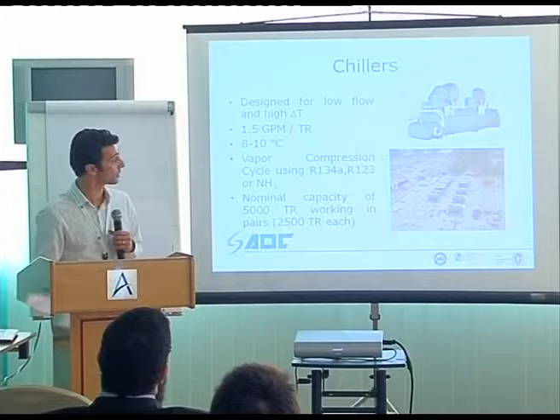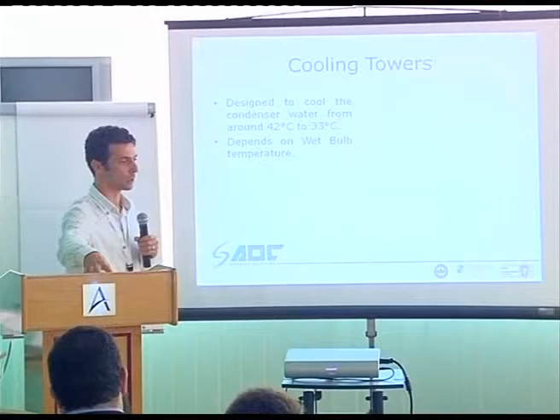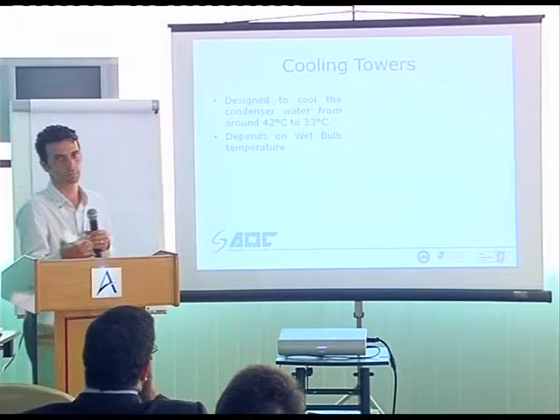We should do another series on cooling towers because they are quite interesting machines. They cool the condenser water from, say, 42 to 33 degrees. Why do we choose the 33 degrees? Because it depends on the wet bulb temperature that we have. I mentioned Riyadh because Riyadh is quite a very low, very dry place, and hence the wet bulb in Riyadh is much lower. In Riyadh, ASHRAE publishes the wet bulb that you need to use as 22 degrees C, where in Abu Dhabi it's around 30.56 or 87 Fahrenheit. And these 10 degrees in wet bulb means a lot to the cooling tower, to the size of the cooling tower, and to the operation of the cooling tower.